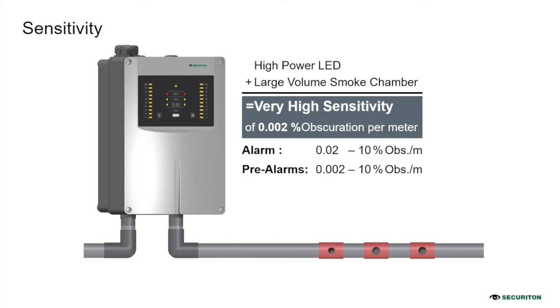So if you talk about the sensitivity, we need a highly sensitive system in this area. The sensitivity can be set from 0.002 to 10% obscuration per meter, and can be adjusted as per the requirement of the customer, as per the temperature inside the valve hall. A very early detection is always required to avoid loss of business operations. Any questions till now?